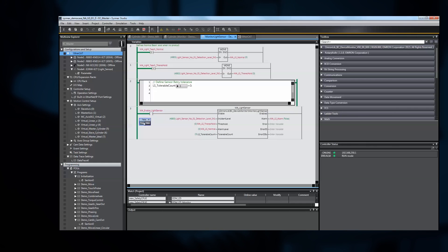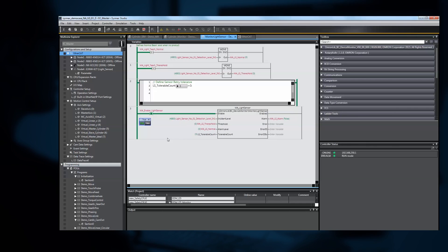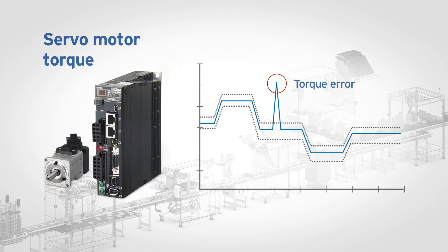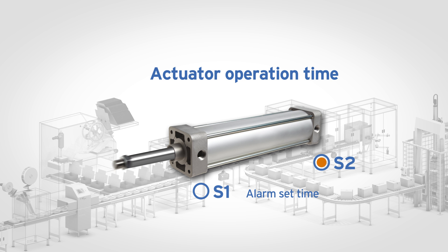Components such as servo drives, actuators, and sensors can all be monitored in real time, and whenever their operation deviates from a normal condition, a warning or alarm is raised before a critical failure occurs. With this function block library, you can easily monitor and evaluate the position and torque response of the servo motor against a normal operating range.